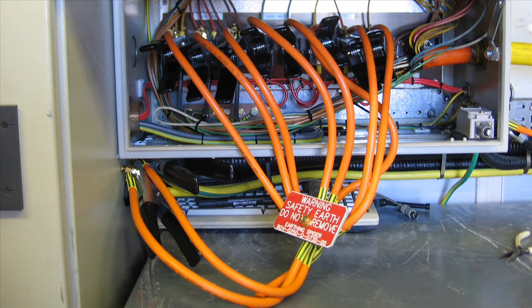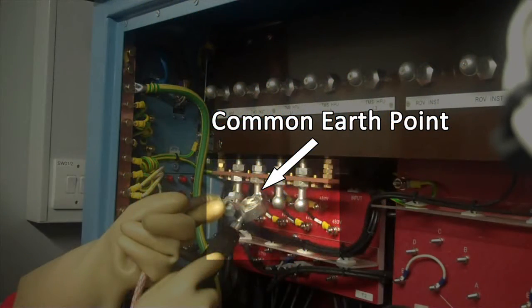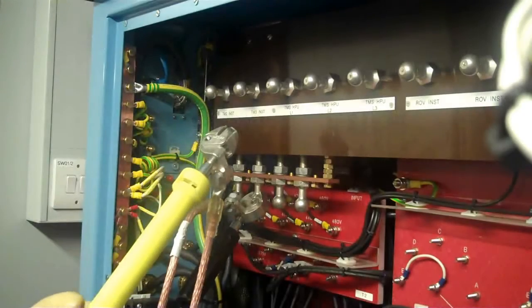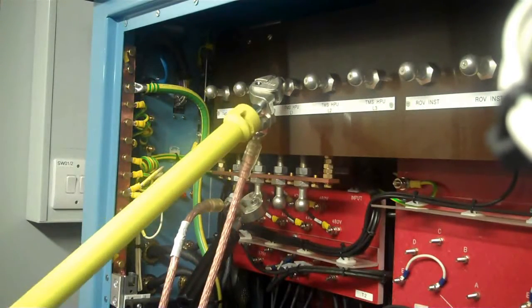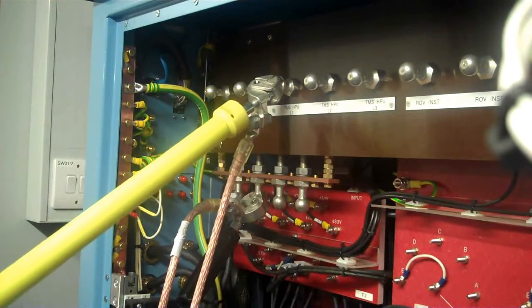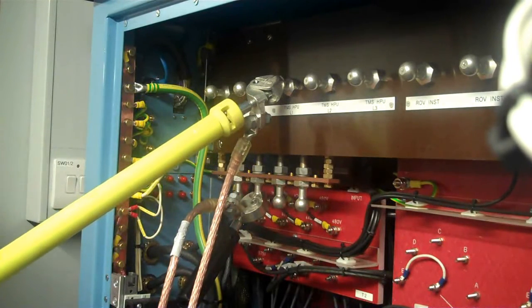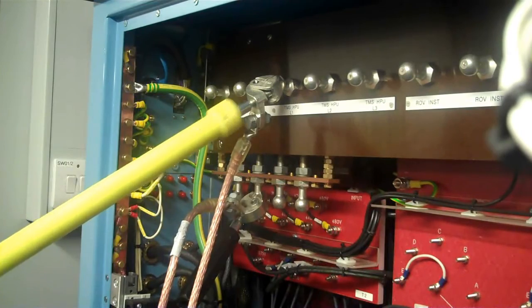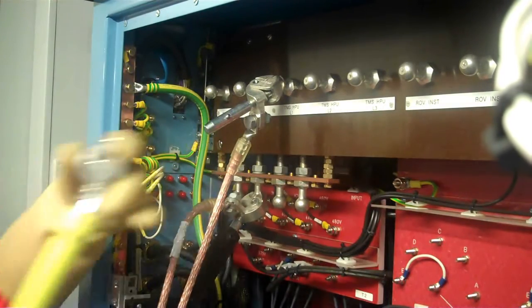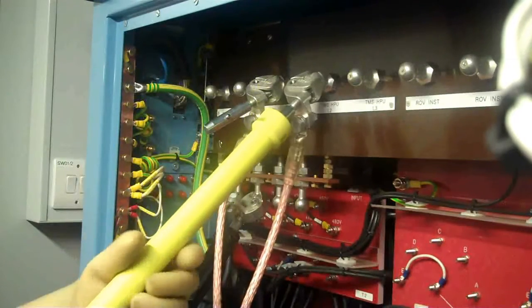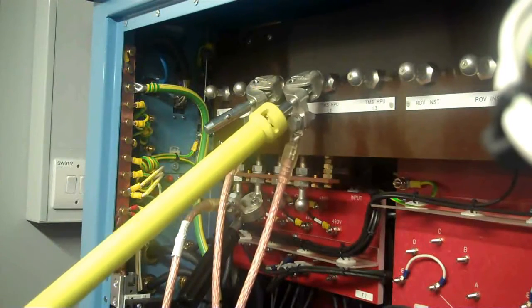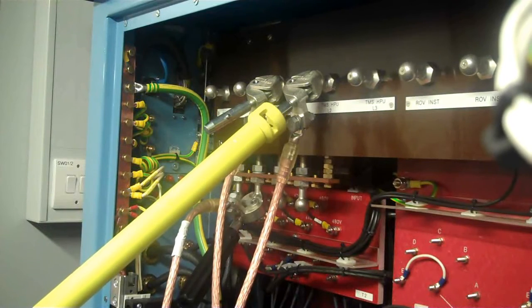The sequence in which the earth leads are connected is important. We begin by attaching a long earth lead to a common earth point. Each additional lead is connected in sequence to the transformer windings or to the connections in the junction box. It is important to be aware of stored energy in cables or cable capacitance and the hazards this poses. For this reason, PPE must always be worn when discharging and attaching earths.